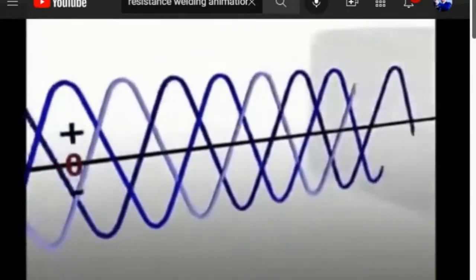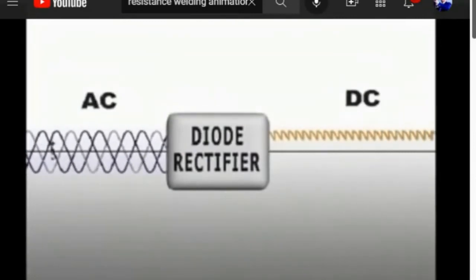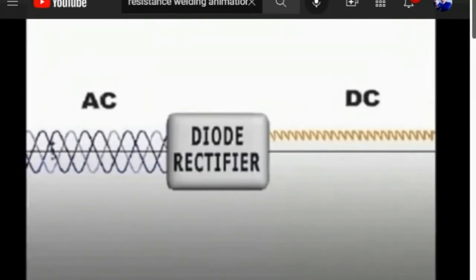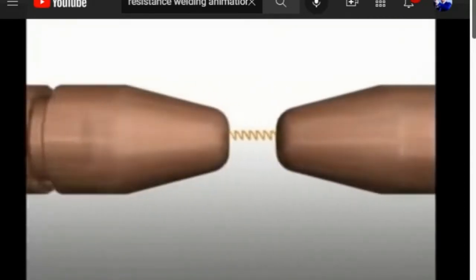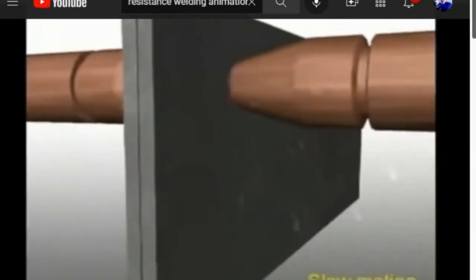To isolate the three phases and make the current more efficient, it can be directed through a device called a diode. A diode allows current to flow through it in only one direction. If a group of four diodes is arranged as a bridge and the AC voltage is connected across it, a bumpy but totally positive polarity ripple results. This process is called rectification and the output is called direct current or DC. The DC wave is much smoother, resulting in less loss, making three-phase DC current better for welding than single-phase AC.